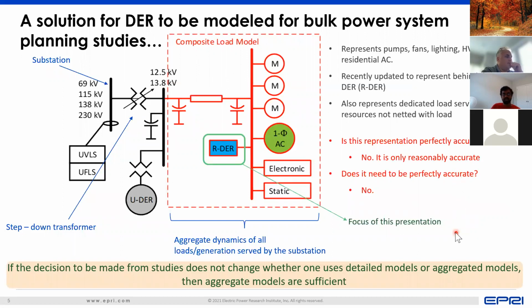So the model that we use is an aggregated model. You essentially have your substation represented, then a substation transformer, and then one level of a three-phase DER, and then an equivalent feeder to represent your distribution network. Then you have lumped loads at the bottom end of this equivalent feeder, wherein these loads could represent different forms of motor load on feeders, lighting load, air conditioner load, pump load. They could represent behind-the-meter DER, essentially rooftop PV, and they can also represent different forms of DER that may or may not be netted with load.